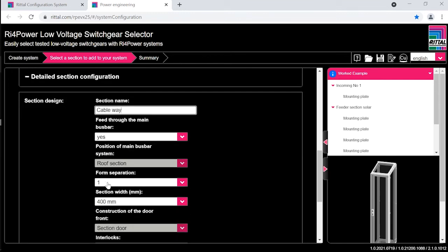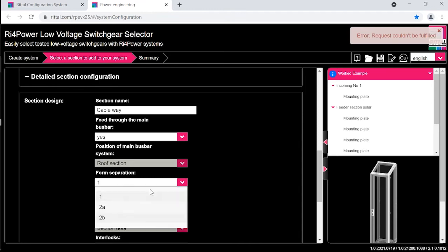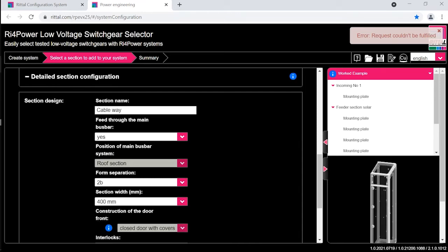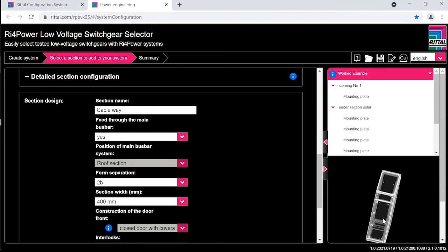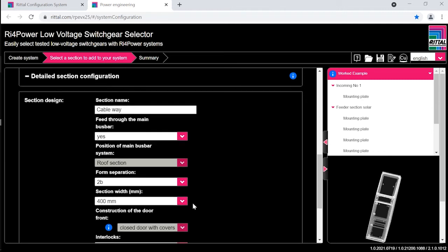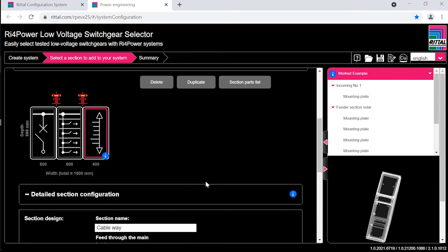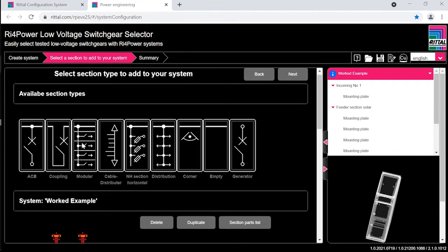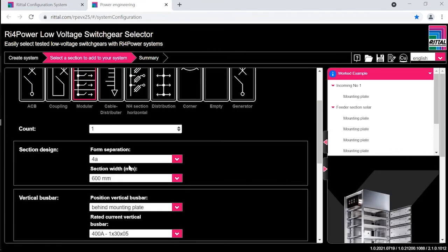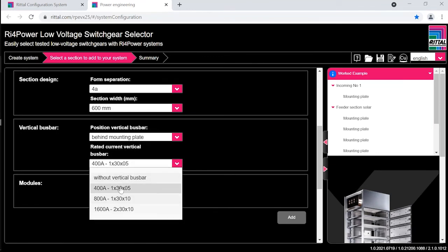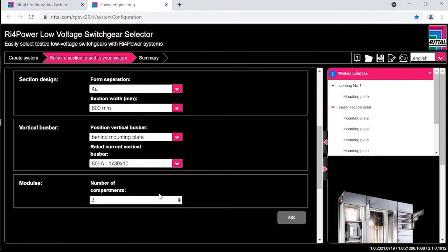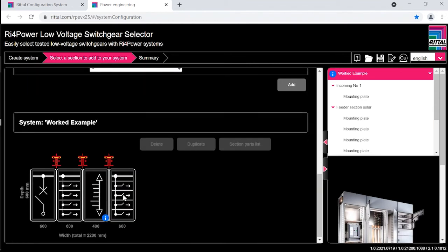Form separation 1. You see from the little 3D drawing there, there's no compartment for the bus bars in the roof, so that has to be changed to form 4 2B. That means the bus bars are segregated from the rest of the compartment. So the bus bars will be in there, and that is your cable way with the cables to drop out through the bottom. So now we need another outgoing section, form 4A again. We want 800 amp behind the mounting plates. Gives you that, which looks good.